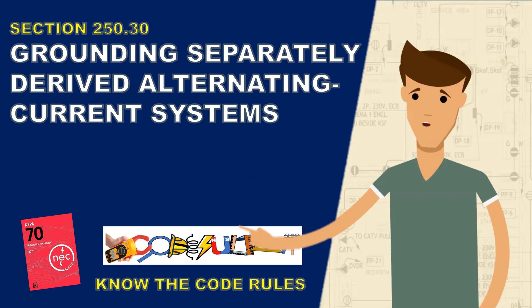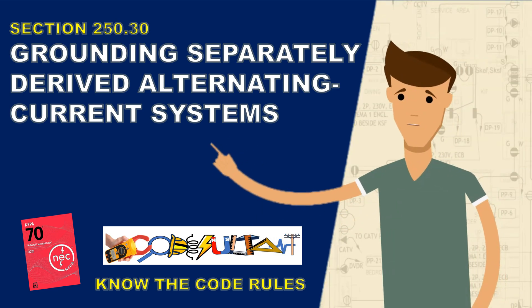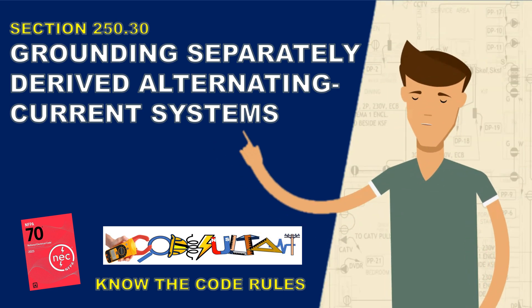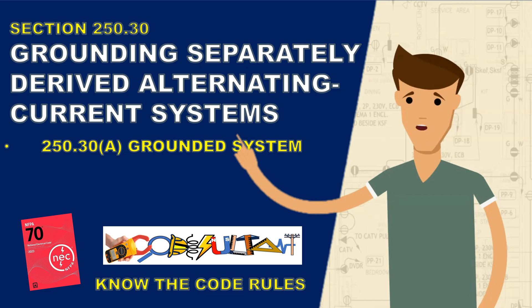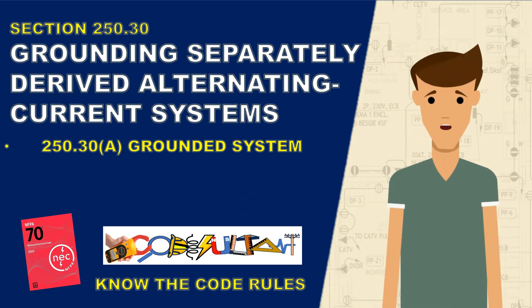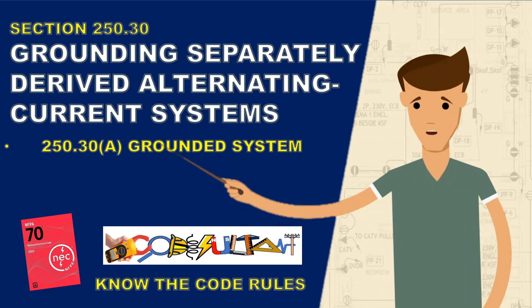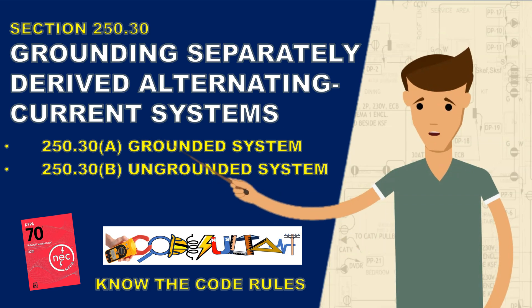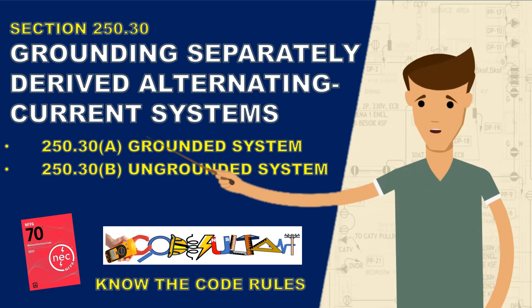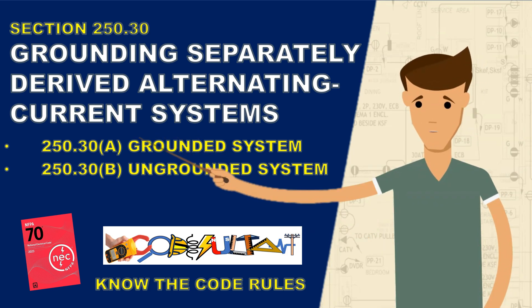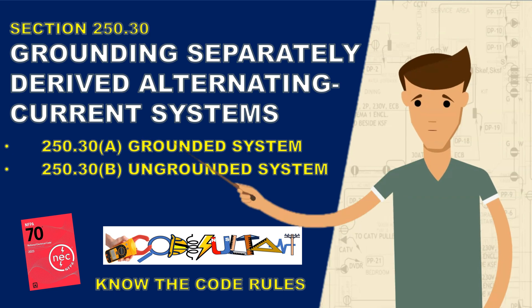Grounding of separately derived systems is divided into two parts. The first part addresses separately derived systems within grounded systems under 250.30 A, and the second part is for separately derived systems within ungrounded systems under 250.30 B.